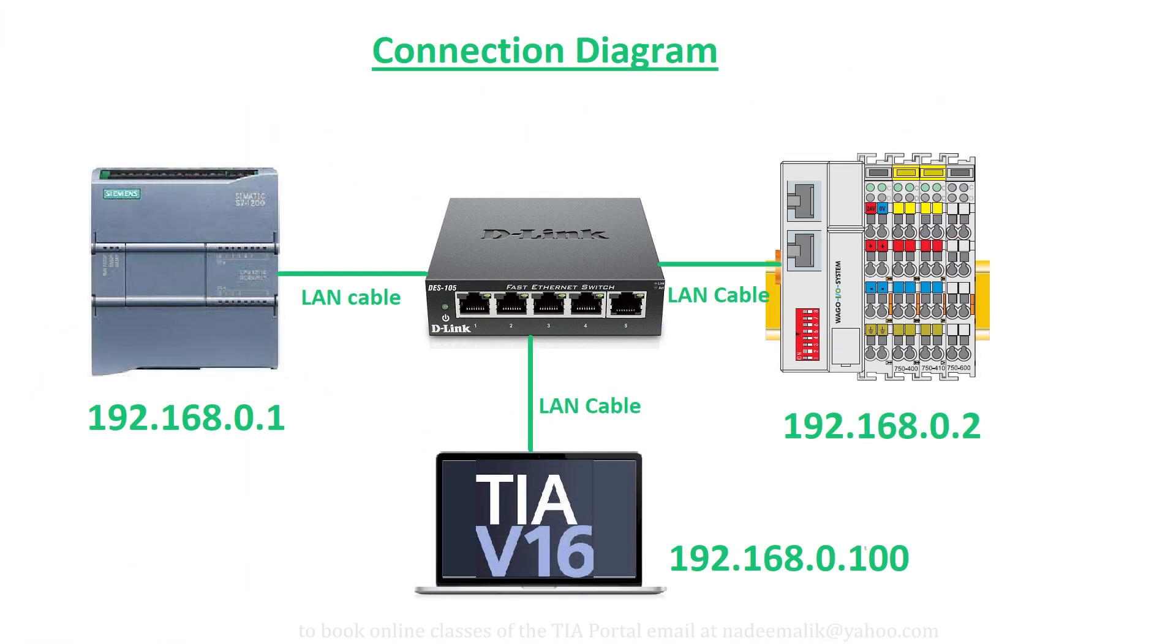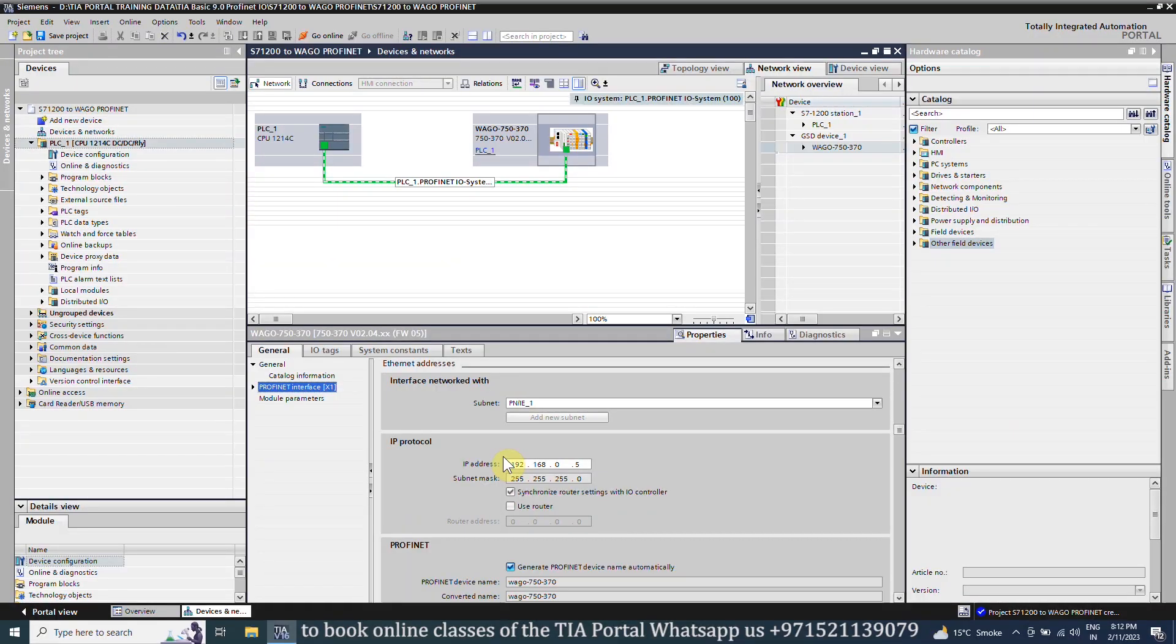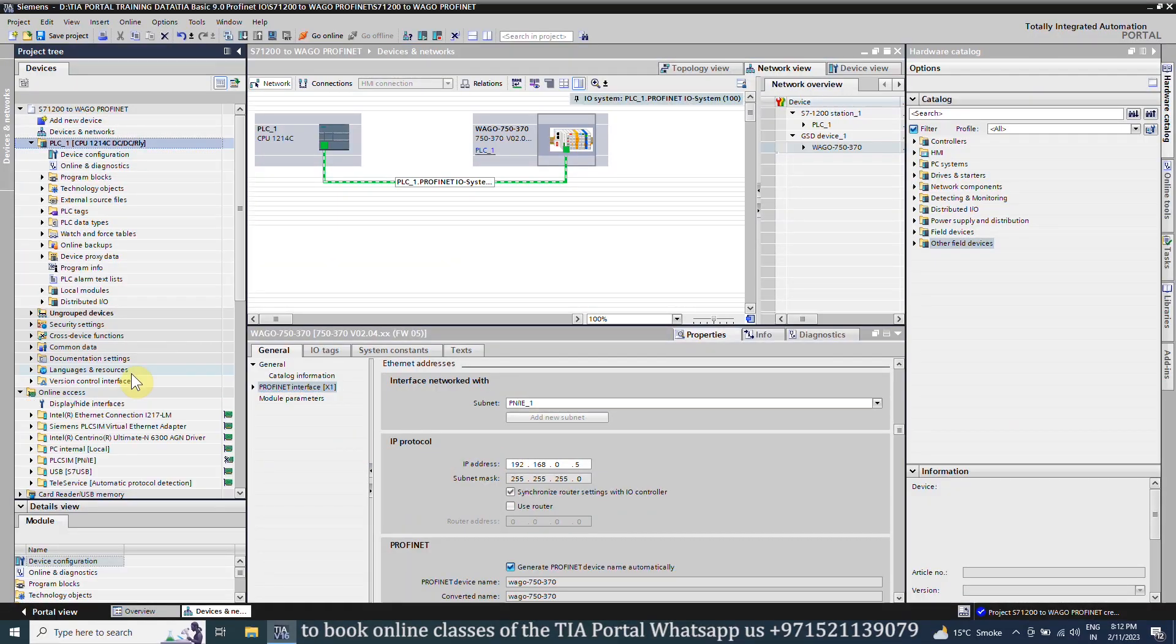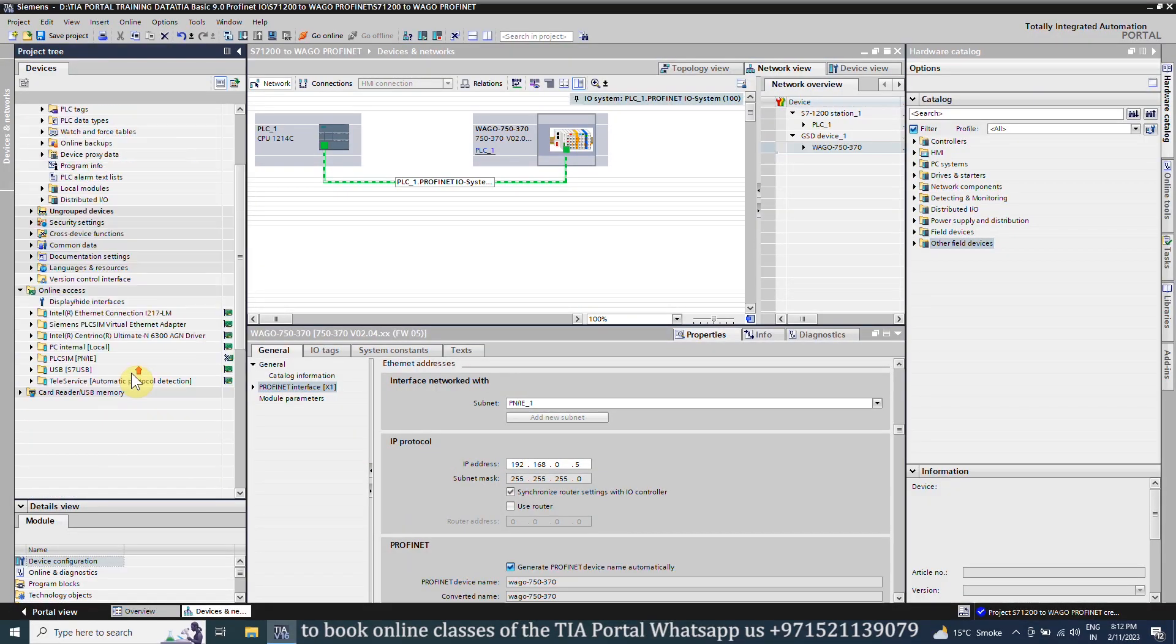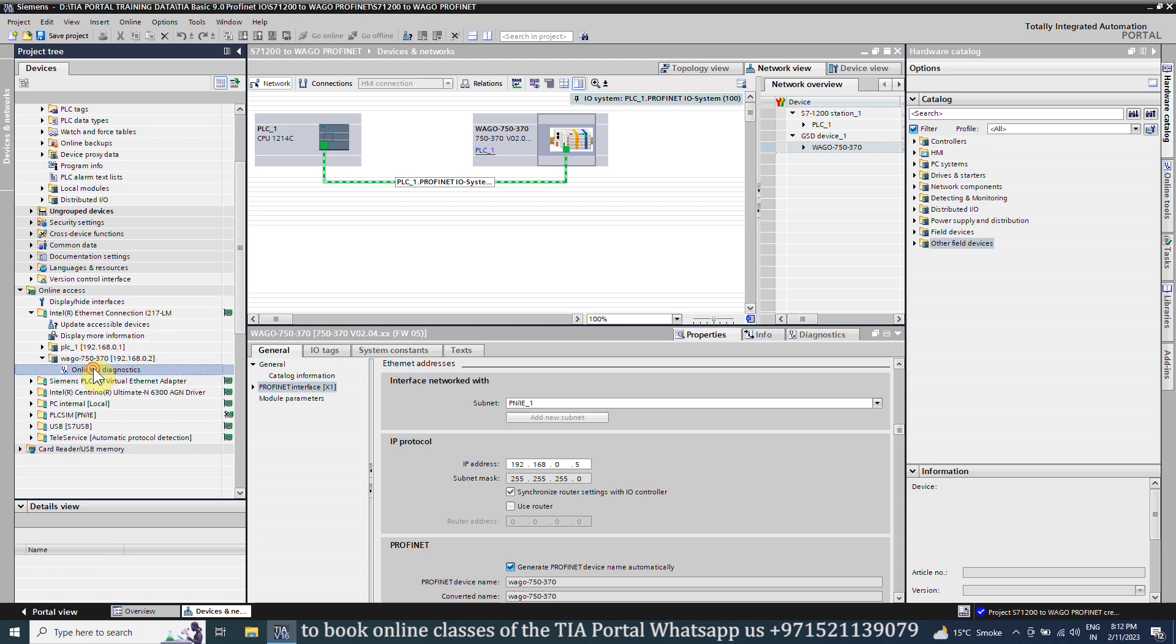As we have connected WAGO fieldbus coupler and the S7-1200 PLC to our PC via LAN card, we can access the fieldbus coupler and assign it the new IP address. We can use the online access option and browse the Ethernet LAN card of the PC.